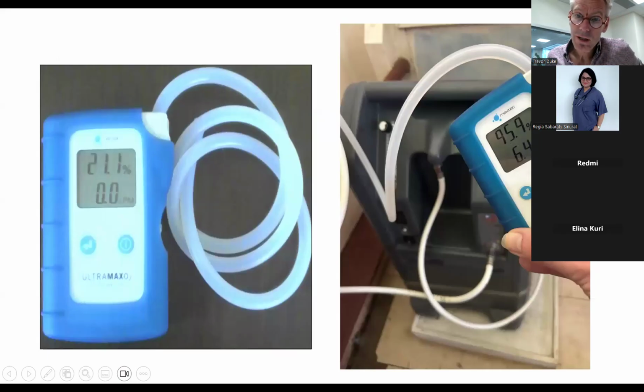I mentioned before, sometimes it's very useful to know whether your oxygen concentrator, whether it's your Diamedica machine for giving CPAP or a standard oxygen concentrator, is actually giving the oxygen you want it to. Many of you will have seen these. These are oxygen analyzers. It's not a pulse oximeter, it's an oxygen analyzer, and it's used to check the performance of your device. When you open them to air, then of course the fraction of inspired oxygen will be 21%.